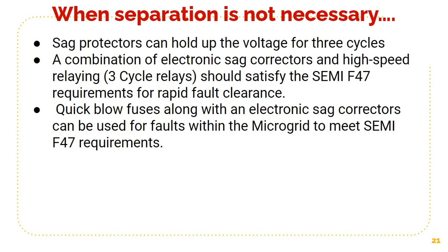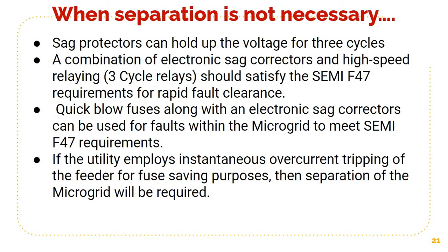Quick blow fuses along with an electronic sag corrector can be used for faults within the microgrid to meet SEMI F47 requirements. So that is another alternate. If the utility employs instantaneous overcurrent tripping of the feeder for fuse saving purposes, then separation of the microgrid will be required. There is no other way.